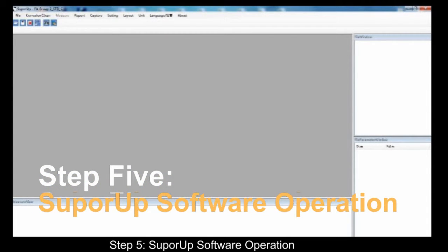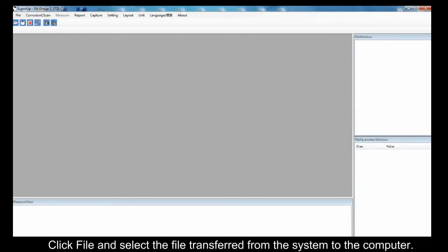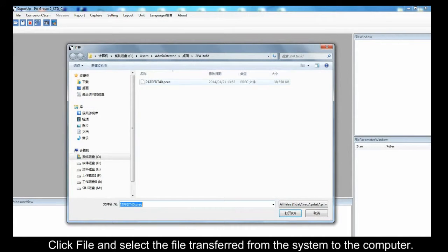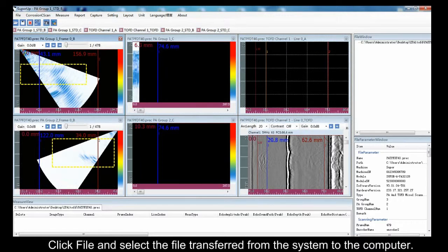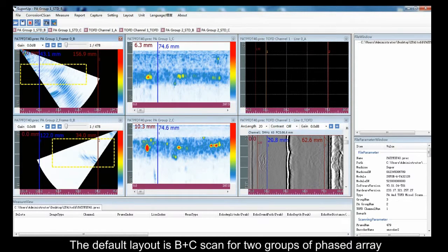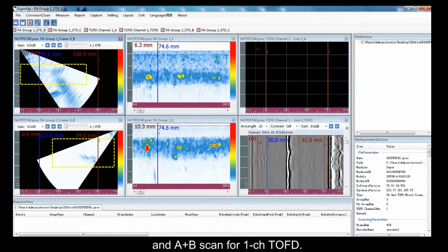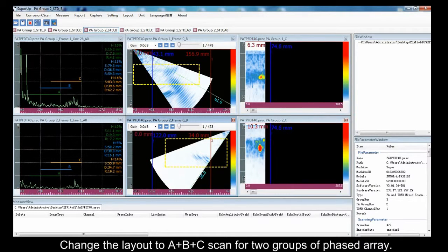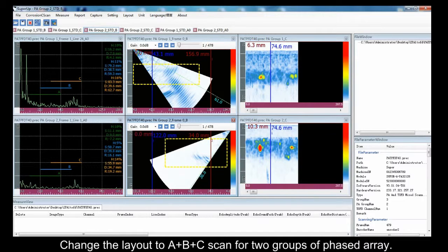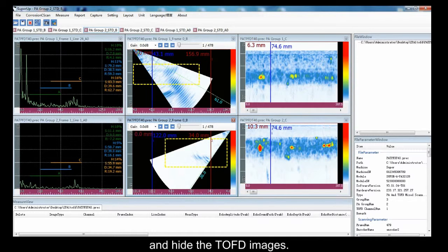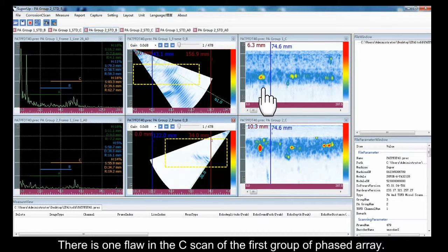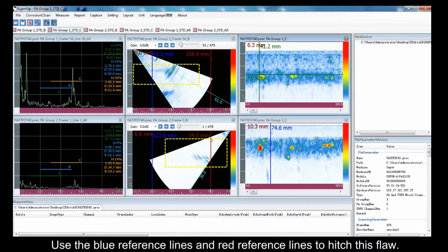Step 5. SuporUp software operation. Click File and then select the file transferred from the system to the computer. The default layout is B plus C scan for two groups of phase array and A plus B scan for one channel TOFD. Change the layout to A plus B plus C scan for two groups of phase array and hide the TOFD images. There's one flaw in the C scan of the first group of phase array. Use the blue reference lines and red reference lines to hitch this flaw.